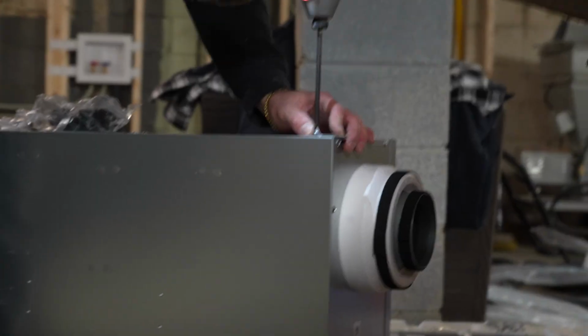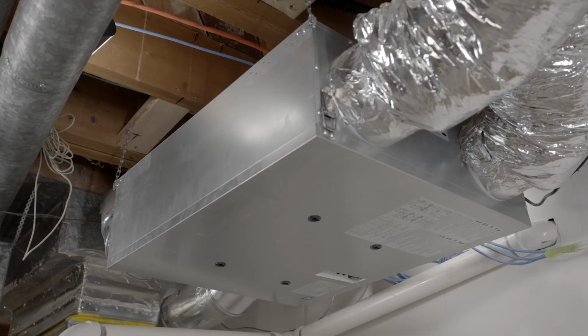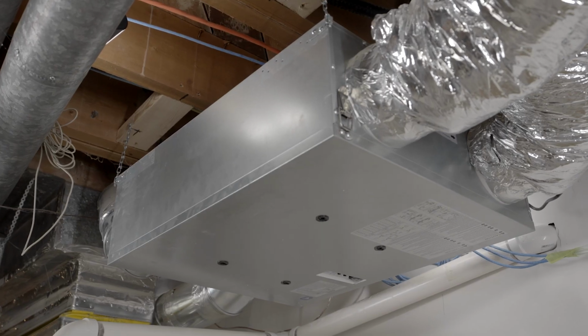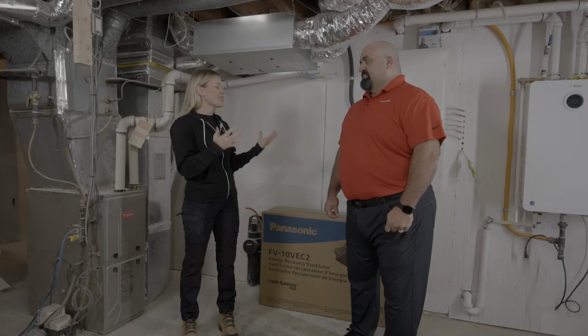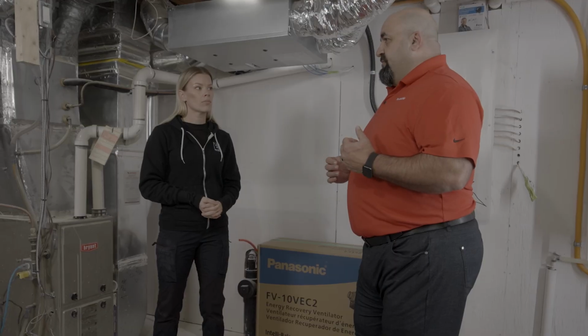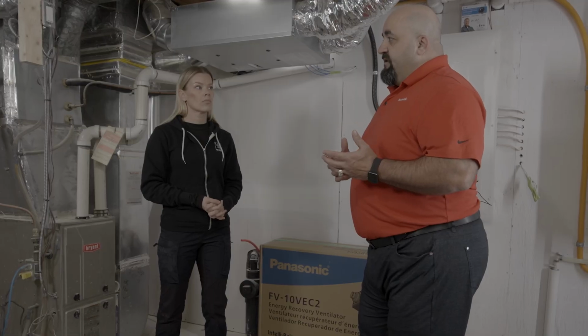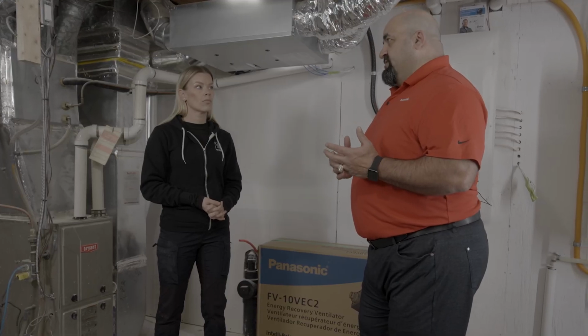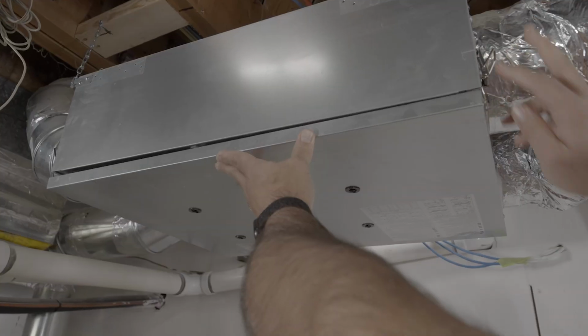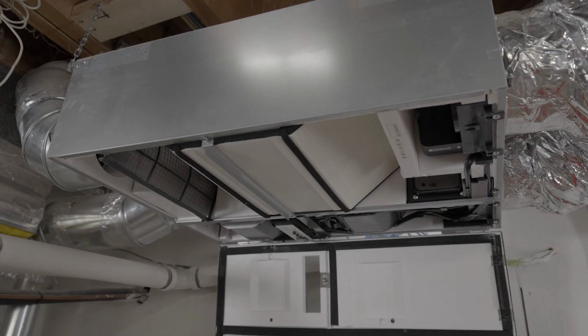So this is the IntelliBalance 100, our fancy name for energy recovery ventilator. What's so important about an ERV system? Well, step back and look at it as an air exchanger: we're pulling in fresh air and taking out stale air. Whether it's a heat recovery ventilator or an energy recovery ventilator, they're doing the same thing, but the key is the core within the unit. With a heat recovery ventilator you're not able to manage moisture as well as with an ERV. The magic is really done within the core of the unit.